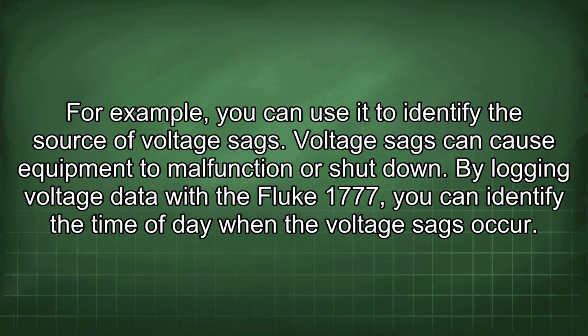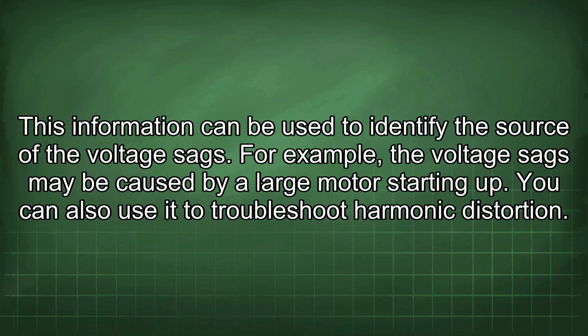Voltage sags can cause equipment to malfunction or shut down. By logging voltage data with the Fluke 1777, you can identify the time of day when the voltage sags occur. This information can be used to identify the source of the voltage sags. For example, the voltage sags may be caused by a large motor starting up.